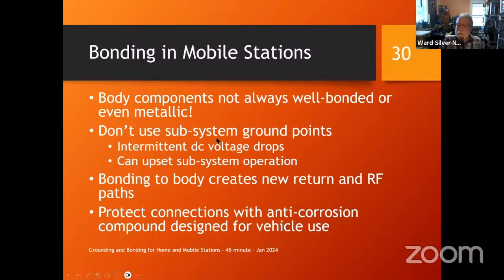Don't use the subsystem ground points - for the computer system or some kind of controller. What happens is you inject all that radio current into that ground point, and the voltage can go up and down a little bit. That can confuse or upset your subsystem operation, and it looks like you've got RFI. You don't have RFI, you have DCI - DC injection into that ground point, causing the voltage to go up and down when the subsystem doesn't expect it. So don't bond to these points.